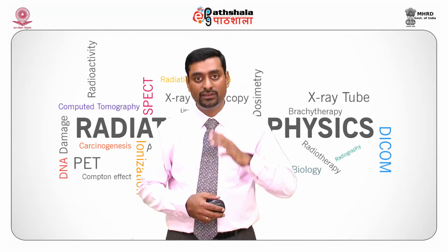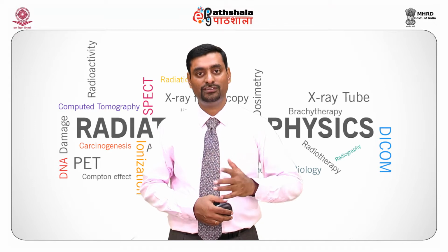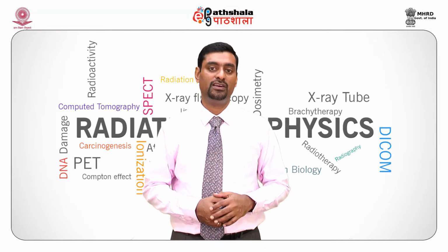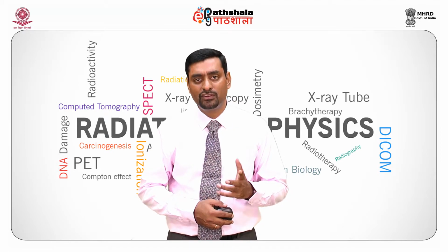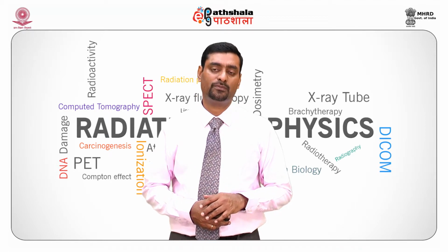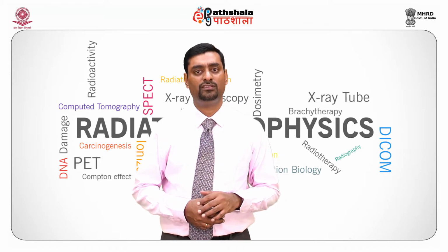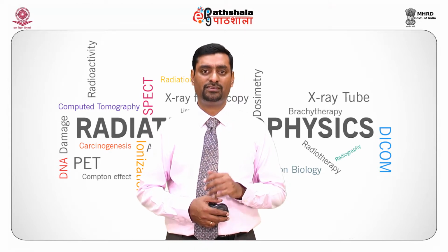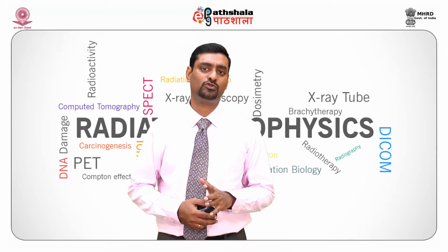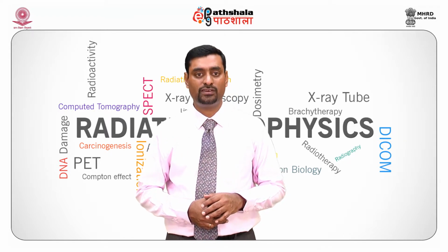That means all the radiation energy is absorbed by the detector material and all the information from the subject is seen on the detector material. So that's the ideal DQE, but we cannot get that kind of ideal DQE. Generally for some of the good systems, we see DQE of about 0.75 or 0.8. Maybe close to 1 is good, but we will not achieve that kind of image quality.